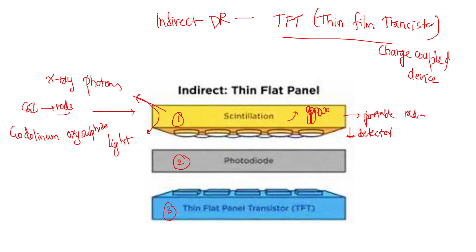The scintillation layer contains elongated crystals of very small size, smaller than the pixel size. The light produced by these crystals is reflected and directed towards the photo diode. A thick layer of scintillator is used to increase detector efficiency. The x-ray photons are absorbed and they release almost 3000 light photons, which are mostly present in the green part of the spectrum.